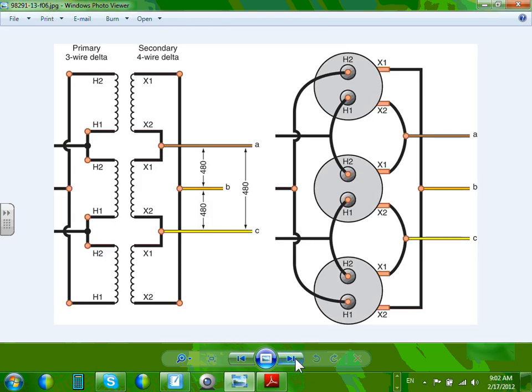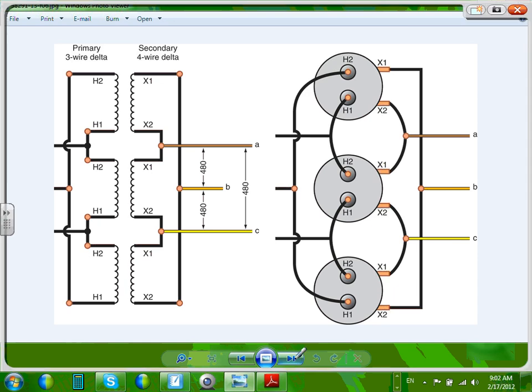So this is a couple of wiring diagrams where you can bank three single-phase transformers to make a three-phase transformer. So I can bank, this is 75 kVA, and another 75, and another 75. Bank them together to get me 75 times 3 kVA and feed a three-phase system. Any question, guys, about banking transformers?